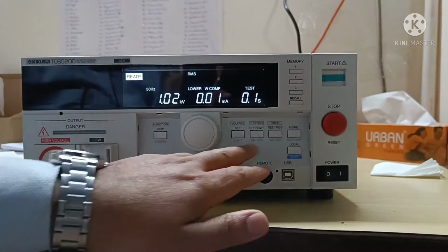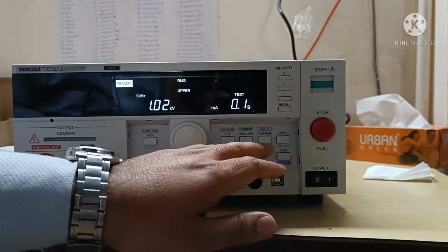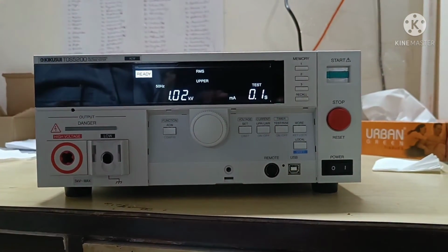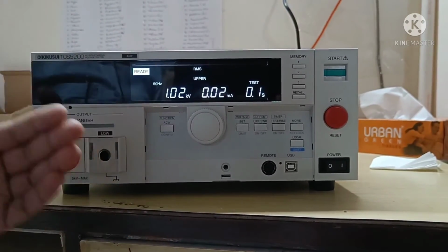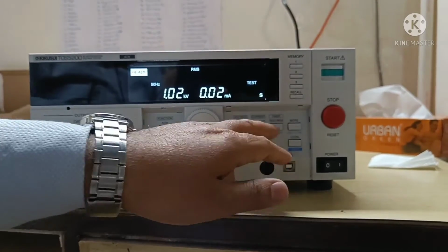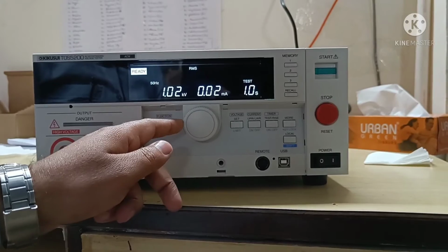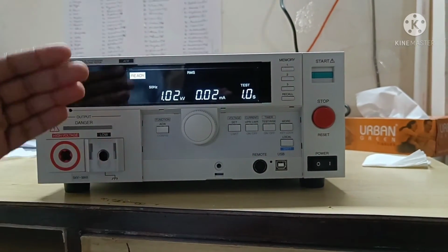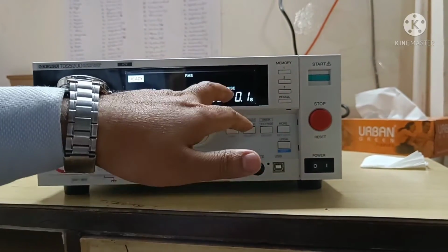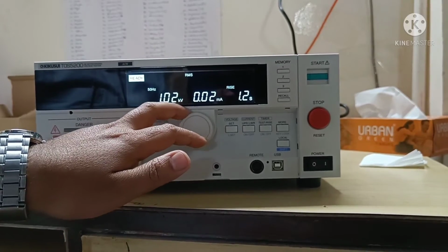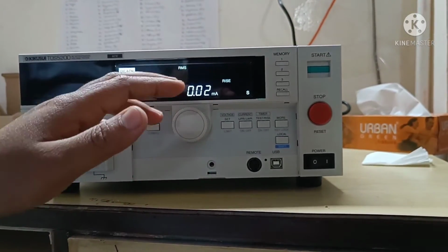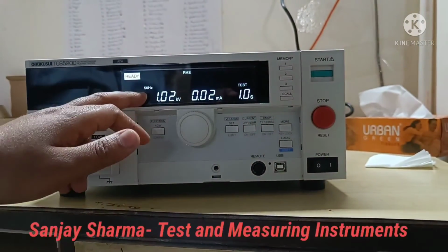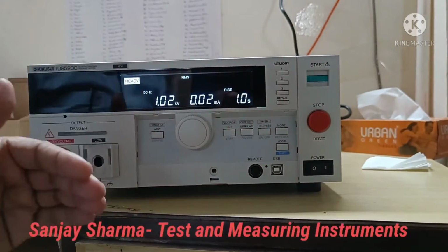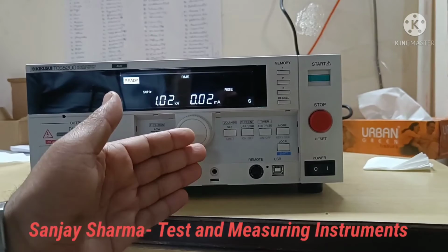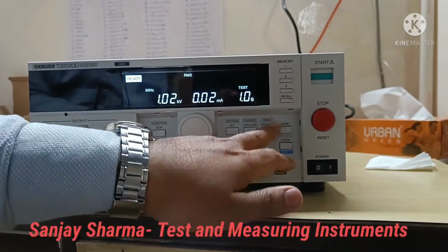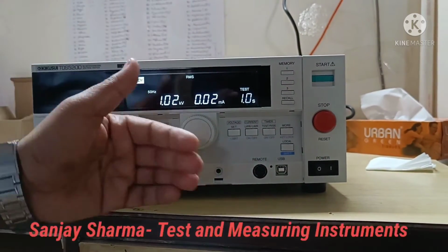So you can use it this way. Right now I'm going to restore the default settings. This is the test time and the rise time function. With test time, you can set how long it will test, up until your setting value. I have set 1 second. It will test for 1 second and then fall down within 0.1 second. That is the default. And here is the rise time. If you set the rise time to one second, and the test time is also 1 second, the voltage will rise to 1 kV in 1 second, then it will test for 1 second. Practically, we will see how it happens.